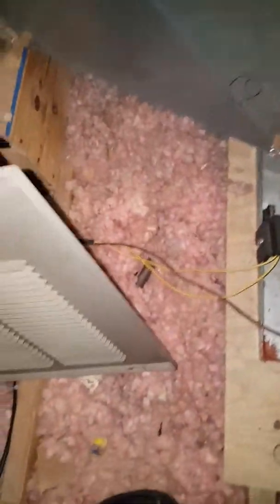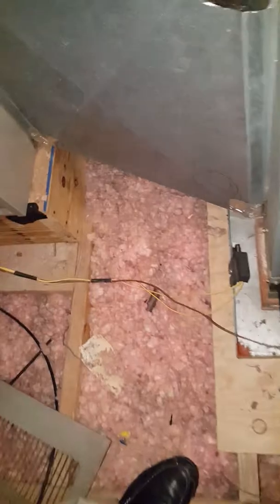The return is here on this end — it goes up and over and some flex ducts run off of that and down to the end, so we've got multiple returns. We've got a four-inch vent that goes up through the roof, and the refrigeration lines. There's a condensate drain with a secondary pan only under the coil, none under the furnace, and there is a float switch on that secondary pan.